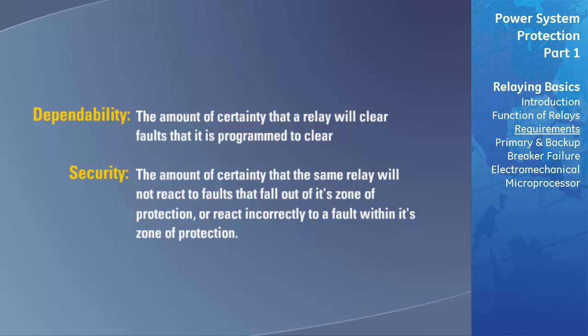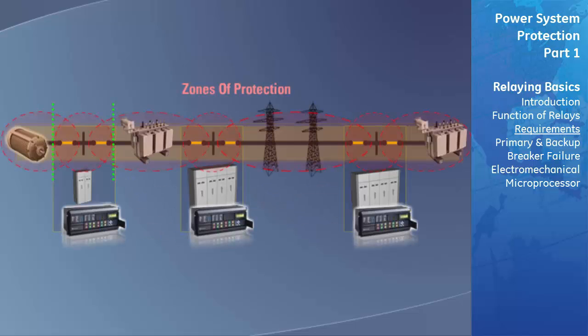Generally, when the dependability of a relay is increased, the security decreases and vice versa. For example, let's increase the sensitivity of one of the relays in our example protection scheme to be as dependable as possible. Now, when a fault occurs within this relay's protective zone, our relay is sure to identify and clear the fault. However, when a fault occurs outside of this relay's established zone of protection, it attempts to clear the fault. This is because the relay has been made so sensitive that it identifies and reacts to faults even though they fall outside of its zone of protection.